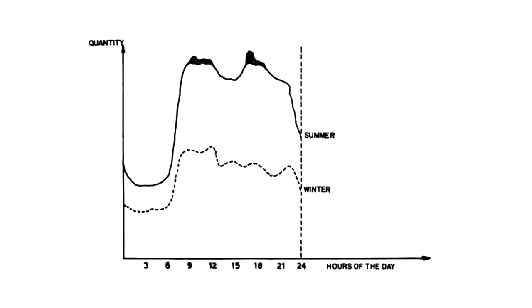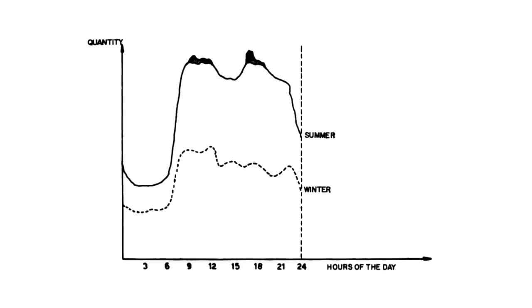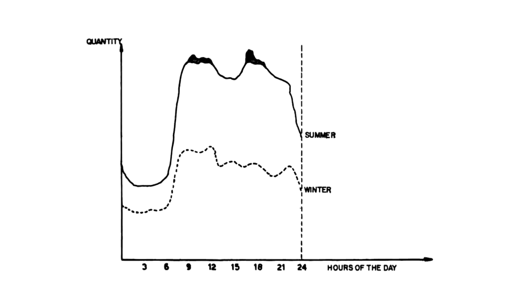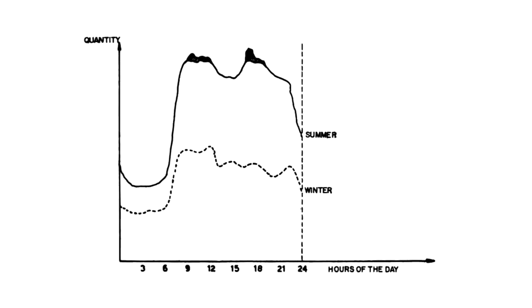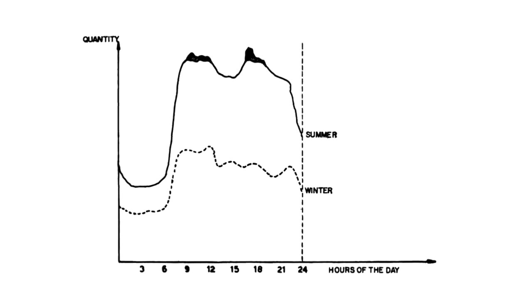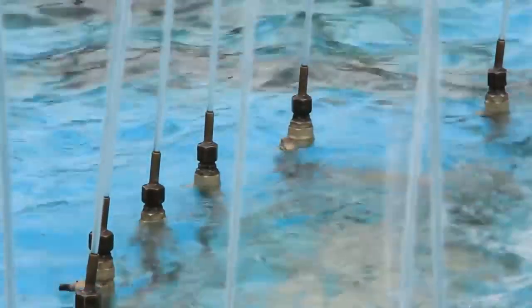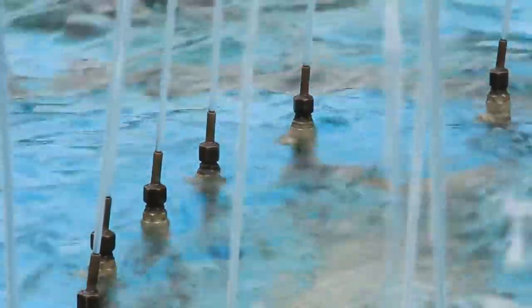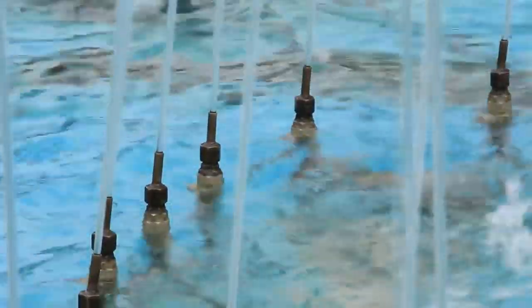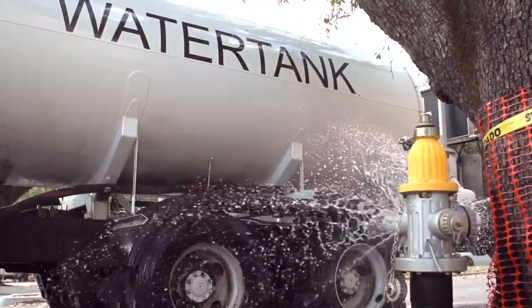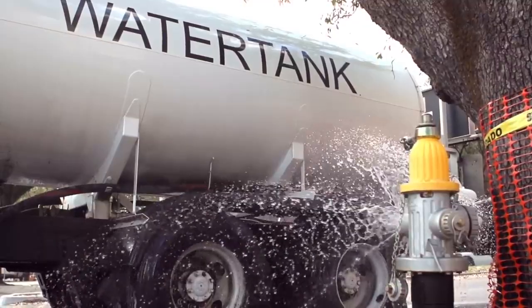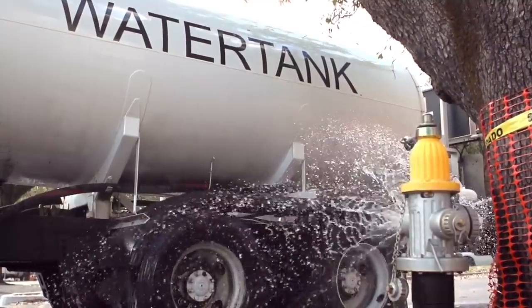Water demand in large urban areas can vary significantly over the course of a normal day, with the peak hourly demand, usually in the morning or evening, sometimes being as much as 5 times the average daily demand. So if you're trying to meet your customers' water needs using just pumps, instead of just one, you might need as many as 5 pumps, or one huge pump that can do the work of 5. And not only that, you'll have to be constantly cycling the pumps on and off to meet the variable demand, increasing the wear and tear on your equipment.